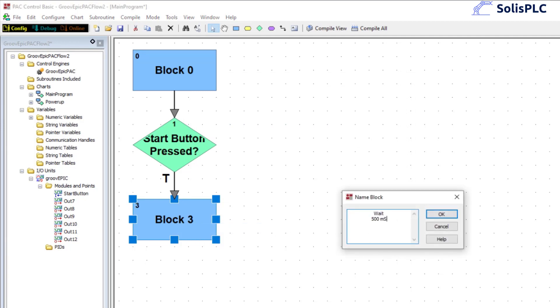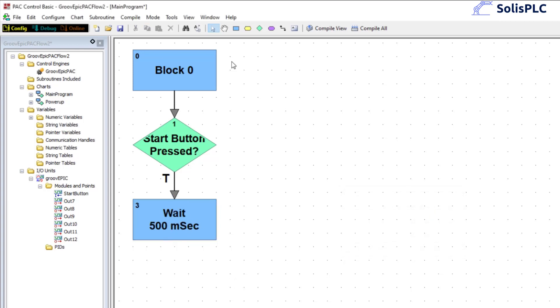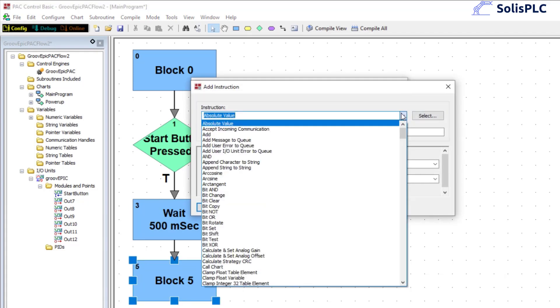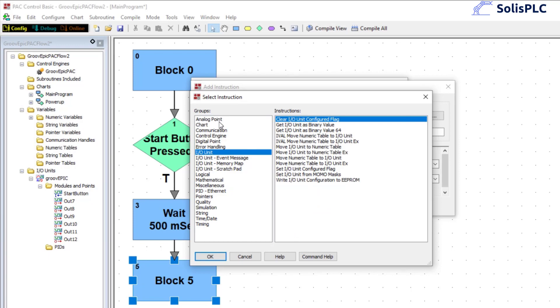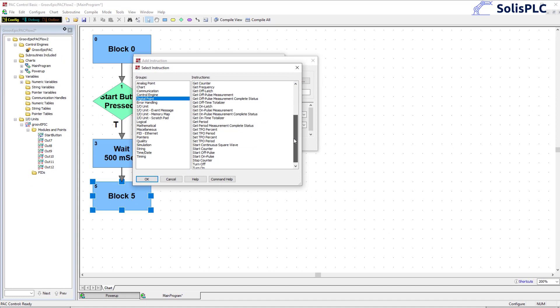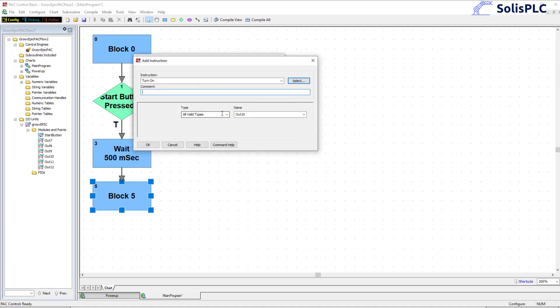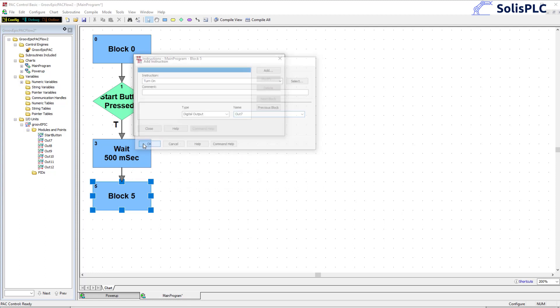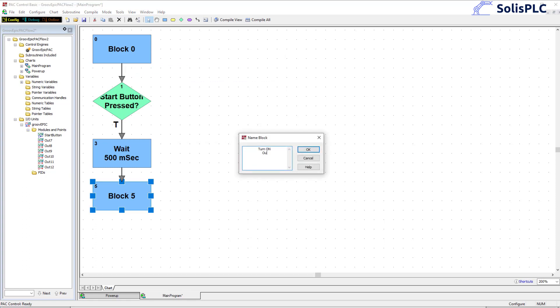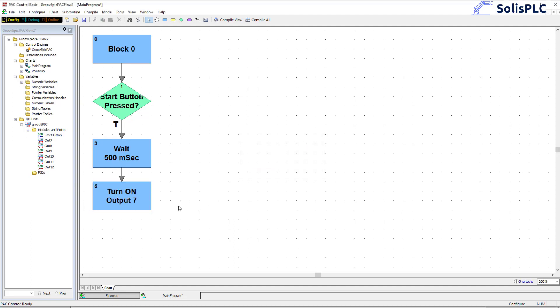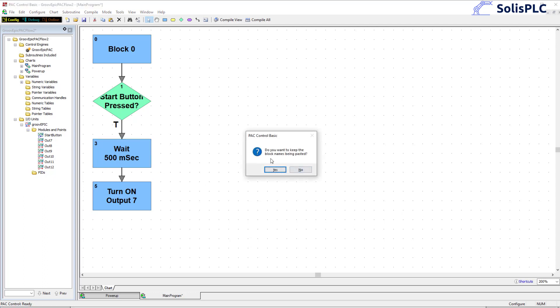We can rename this block 'wait 500 milliseconds' and press OK. The next block is going to turn on the output. Press Add and use Select — IO unit, digital point, turn on. Press OK, select output 7, press OK. We can double-click and rename this block 'turn on output 7'.